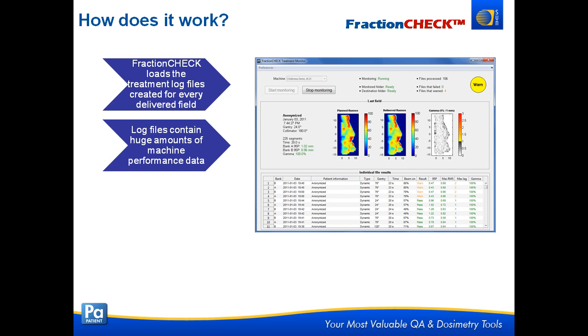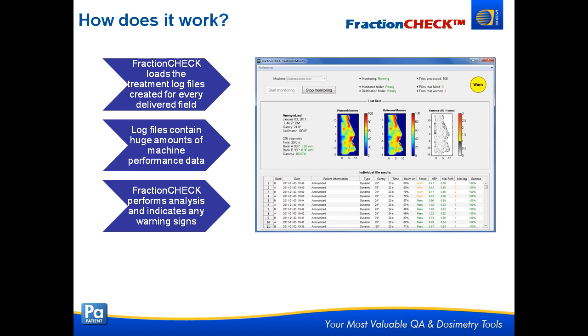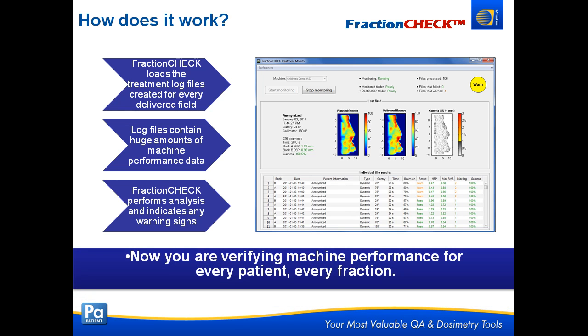These log files contain enormous amounts of machine performance data — just one of them usually contains hundreds of thousands to millions of results. We have to analyze all of those results, apply pass/warn/fail tolerances to everything, and then give the physicists summaries of what happened, indicating if something warned or failed. FractionCheck is very good at summarizing all this information, and once we do that, we're performing machine performance QA for every patient and every fraction they are treated in just a couple of minutes.